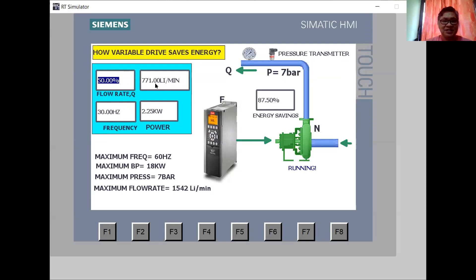At 50%, you can see you have a 30 hertz frequency supplied to the motor by the VFD. You have 771 liters per minute, the flow rate changes, and you are actually using 2.25 kilowatt of the 18 kilowatt power. And then you have an energy saving of 87.50%. This can be put in an HMI, a human machine interface, to see the real-time savings while running. And you can compute this by multiplying the cost of power.